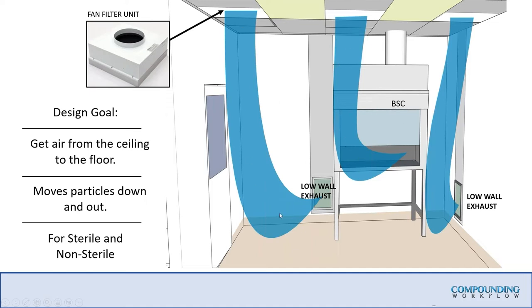The design goal is again to move air from the ceiling down to the floor, and this applies to non-sterile as well, even though it's not specifically called out in Table 2 of USP 800. When handling dry APIs — powders, capsules, troches, creams — technicians repeatedly pull their hands out of the powder, aerosolizing micron-size particles. That airflow should push those particles down to the floor, which in a non-sterile environment must be cleaned every single day per USP 795, demonstrating the interconnectedness of all three chapters.